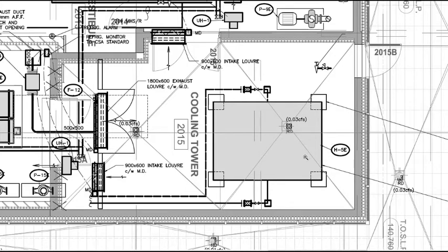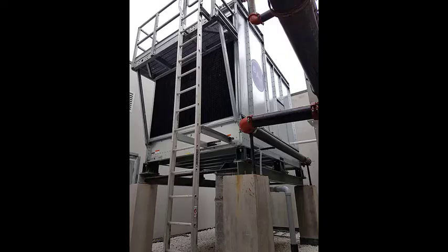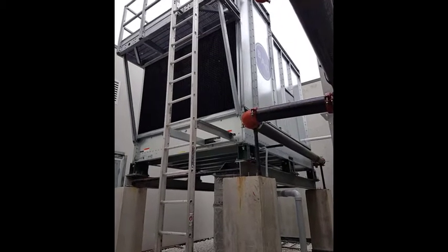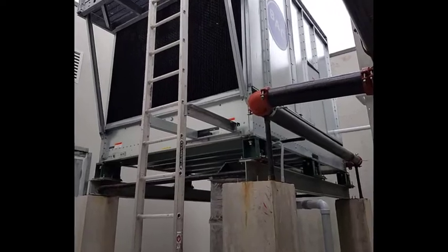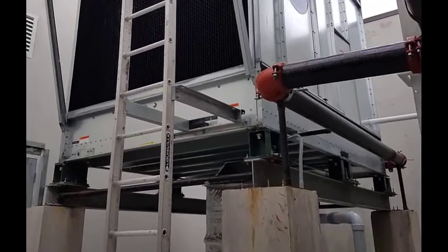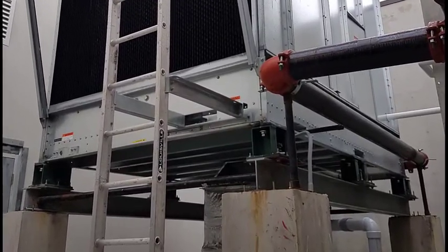As required by the project documents and as recommended by the acoustical consultant, this cooling tower is supported by restrained spring isolators, specifically 2-inch deflection SCSR isolators, complete with neoprene pads under the base plates.